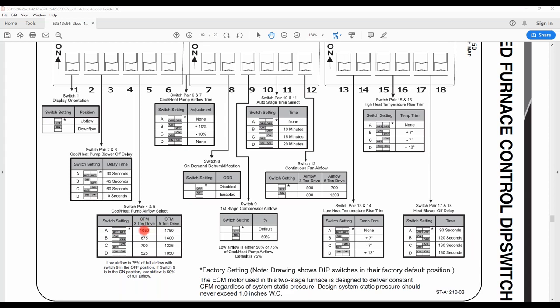If we focus on the 3-ton drive, you're going to get 1,050 CFM. They're figuring approximately 350 to 375 CFM per ton at that point, doing a little bit more dehumidification with the air conditioner. If you want to lower it, change switch number 4 to on and switch 5 to off. That'll lower your airflow to 875, which gets it more in line for a 2-ton to approximately a 2.5 ton. You can see it goes as low as 525. And then you'll see on the 5-ton drive, 1,750 is high, 1,050 is low.